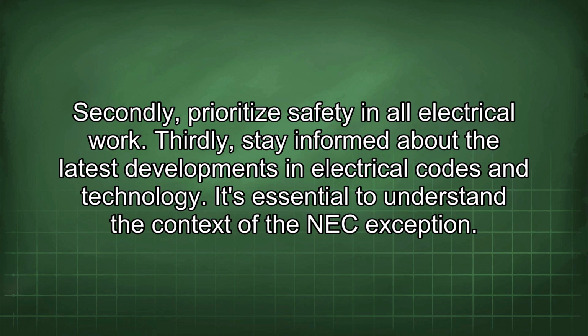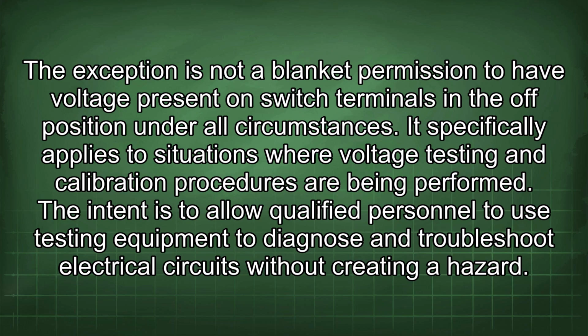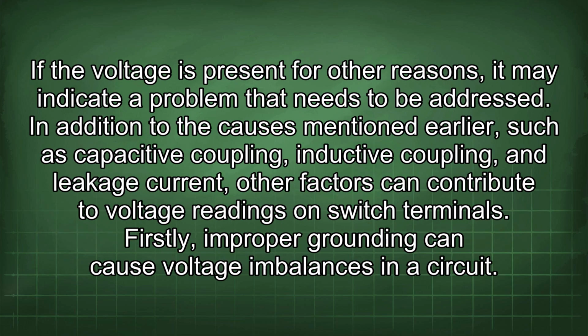It's essential to understand the context of the NEC exception. The exception is not a blanket permission to have voltage present on switch terminals in the off position under all circumstances. It specifically applies to situations where voltage testing and calibration procedures are being performed. The intent is to allow qualified personnel to use testing equipment to diagnose and troubleshoot electrical circuits without creating a hazard. If the voltage is present for other reasons, it may indicate a problem that needs to be addressed.